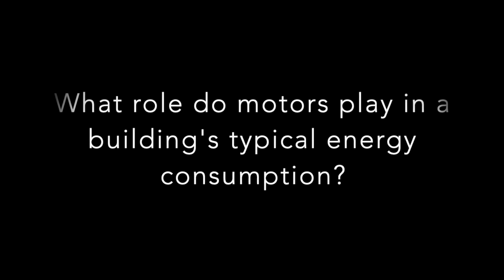What role do motors play in a building's typical energy consumption? There's not a huge amount of knowledge I've found about the amount of energy motors consume. If you take a typical office building, 40% of the electricity it consumes is in heating and ventilating, HVAC. Of that, 50% of that energy is in fans, in motors, driving air around the building. So typically a building will spend 20% of its electricity on electric motors that drive air around the building.